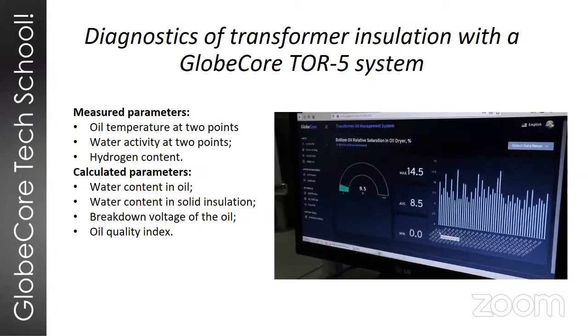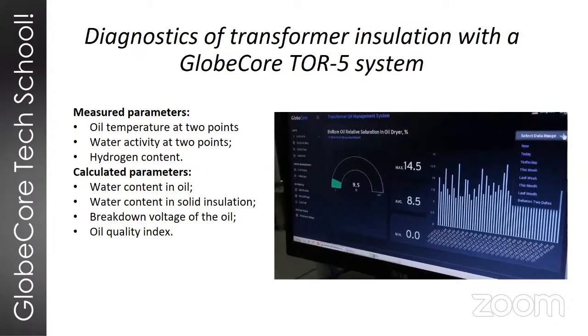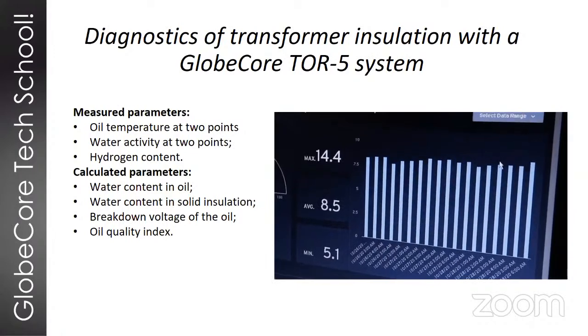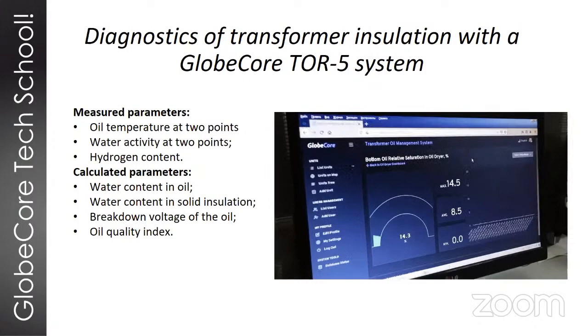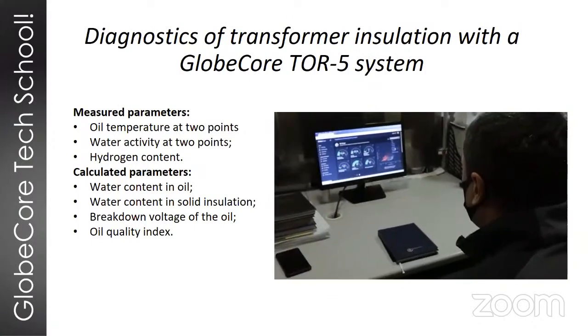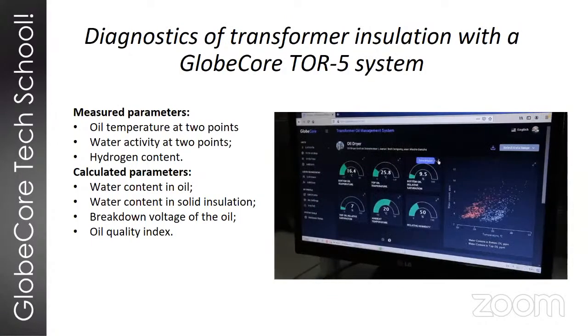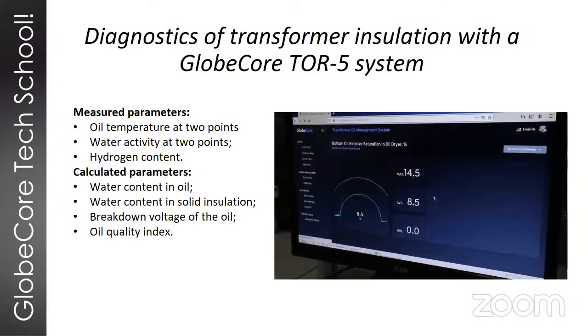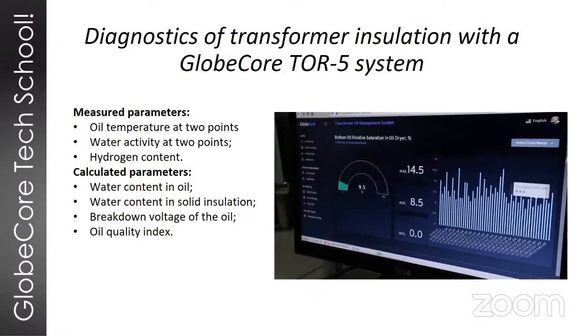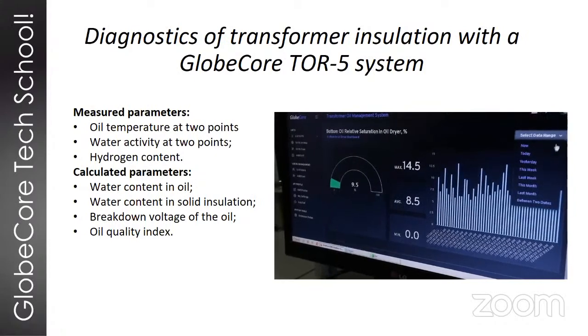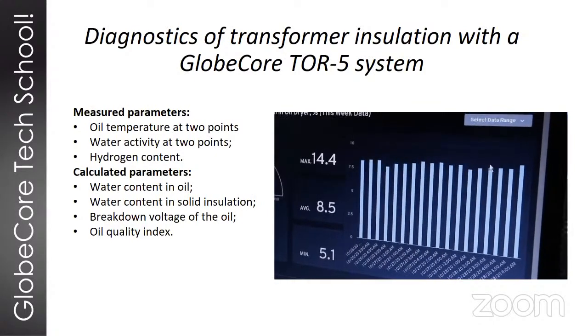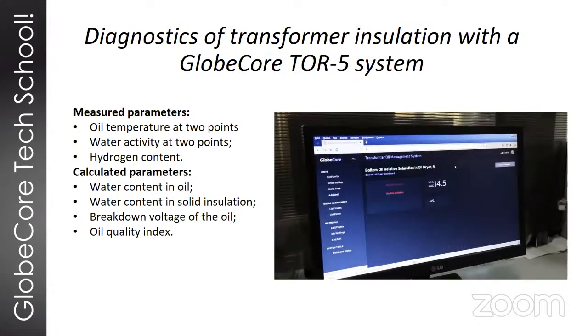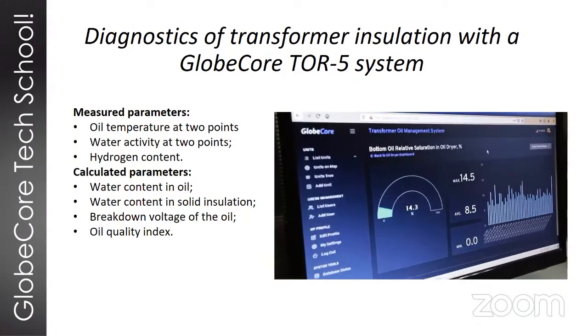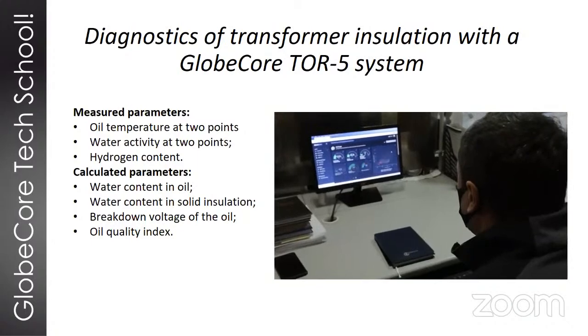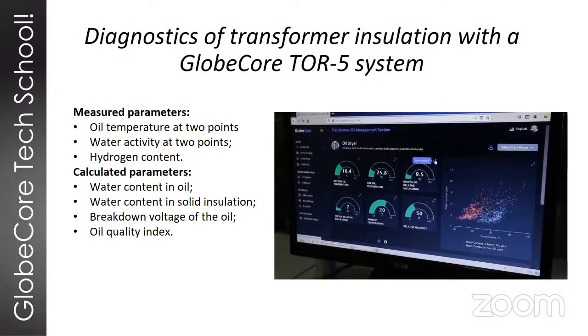It forms at about 150 Celsius, and it constitutes up to 59% of all the gases that are emitted when oil molecules break. So the content of this gas in insulation oil is a very informative parameter for diagnosing possible problems in the transformer, especially for partial discharges. So when you have partial discharges, the weakest hydrocarbon links in the molecules break down and release that hydrogen that we can later measure. Next slide, please.